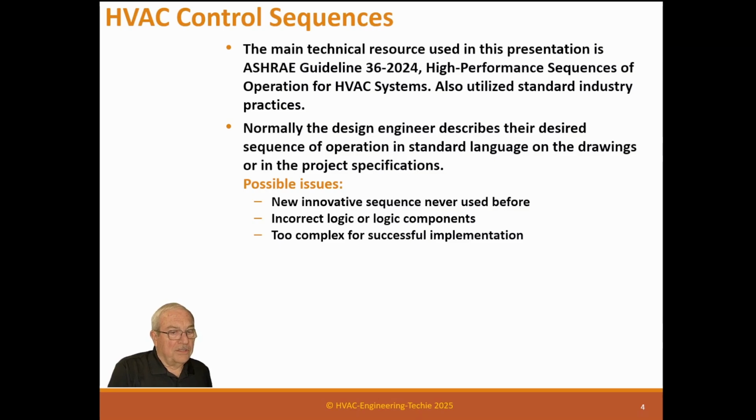I've seen some young engineers do sequences that are so complicated they can hardly ever be written. I mean, I've seen it where they have like 5 or 6 different ranges for a reset. How do you do that? I mean, 2 is hard. 4 or 5 is impossible, and it's not necessary. So that's kind of something we look at.